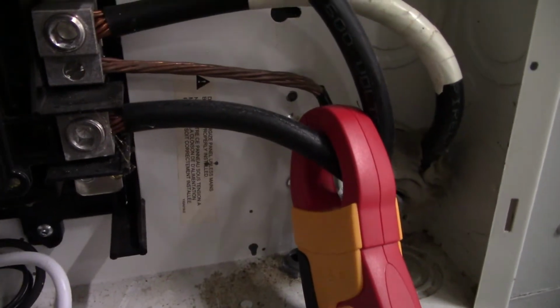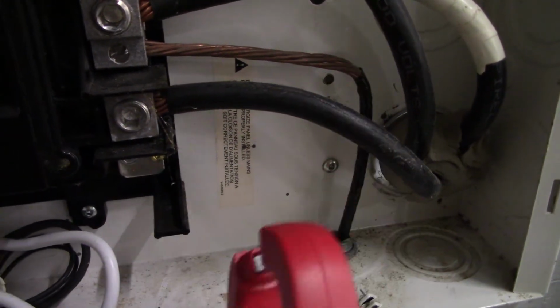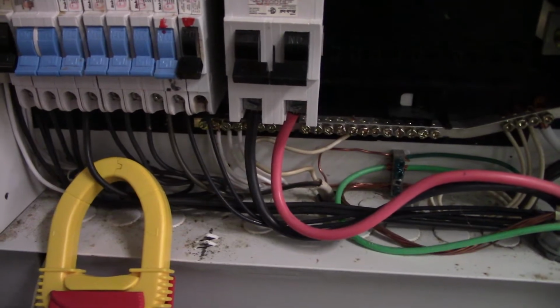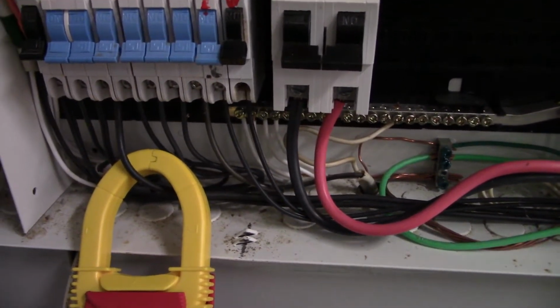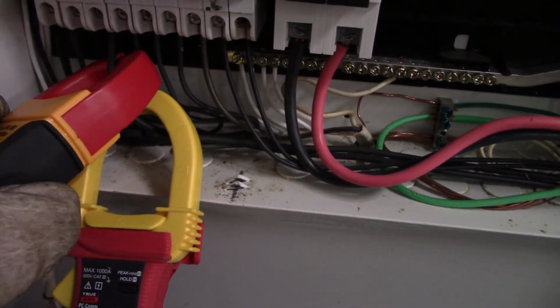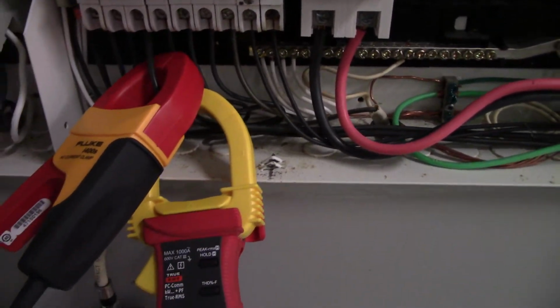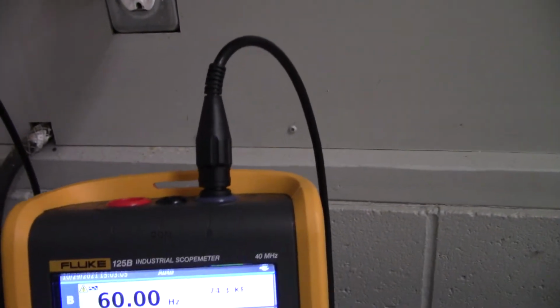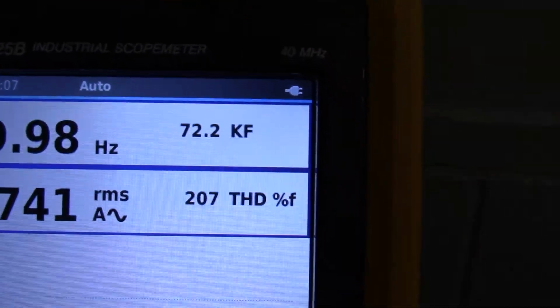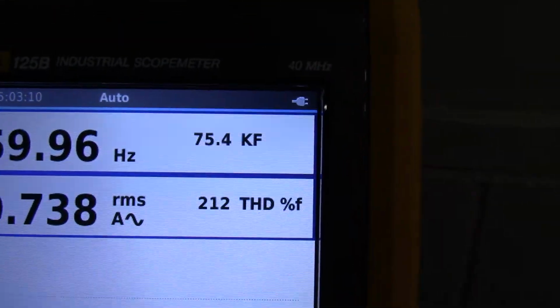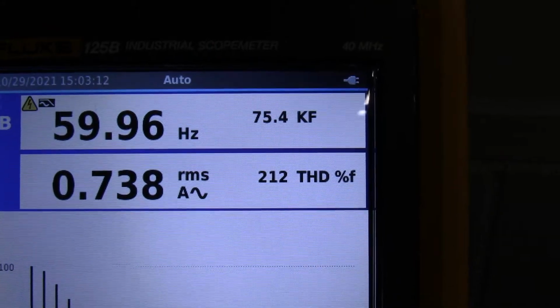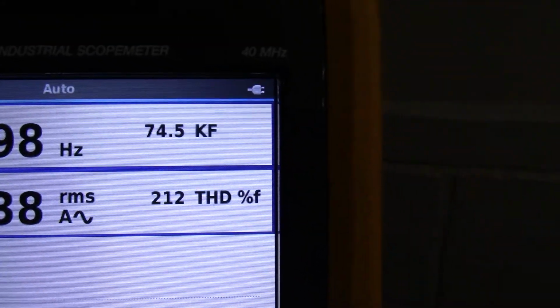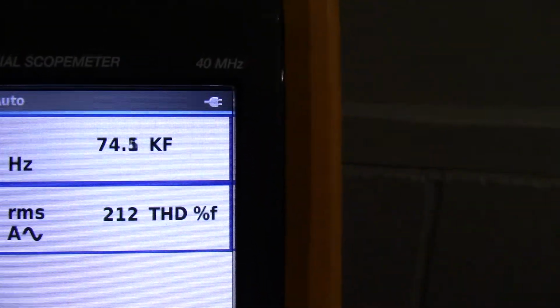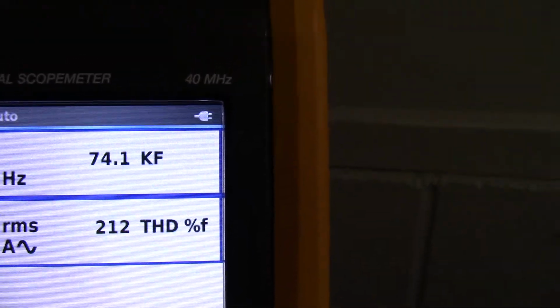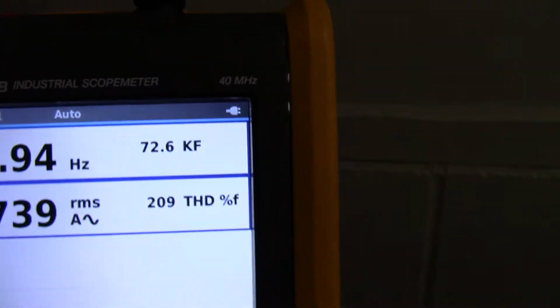So what I'll do now is I'll take this clamp meter from the Fluke industrial scope meter. I'll put it on the same wire. I have to get my polarity right here. And we're going to look at the readings on the Fluke industrial scope meter. And we have 0.74 amps, we'll say, and around 212% THD, total harmonic distortion.